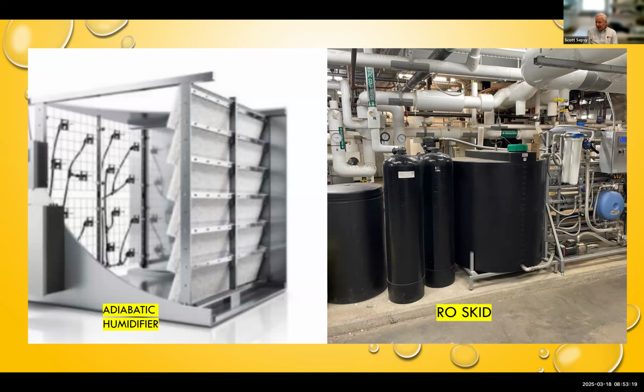We've used direct steam injection isothermal humidification up until now, but if there's space in an air handler, and if you're not using steam in the building for other processes, then we're likely to switch to adiabatic humidification. We're still on a learning curve with these systems, and there seem to be 3 major vendors, and we've used all 3 on the campus and are tracking their performance. These humidifiers require reverse osmosis water, which can be produced on a central humidifier skid shown here, and distributed to various air handling units with local controllers.